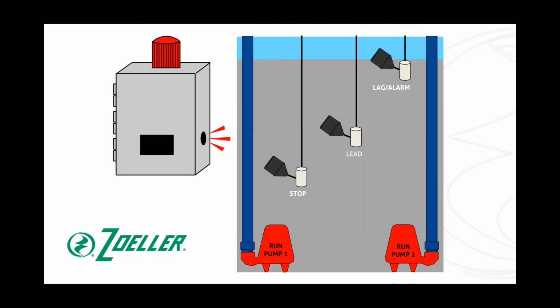Now in this example, I'm going to say that pump 1 was not able to keep up with the water flow that was coming in. It was an unusually high incoming water flow rate. So the water continued to rise in this pit until it reached our lag/alarm float switch. Now at this point, when this float switch is activated, 2 things have happened. The high water audible alarm and visible alarm have been activated, and pump 2, our lag pump now, has been called into action. So we have a lead pump and a lag pump in a duplex system.